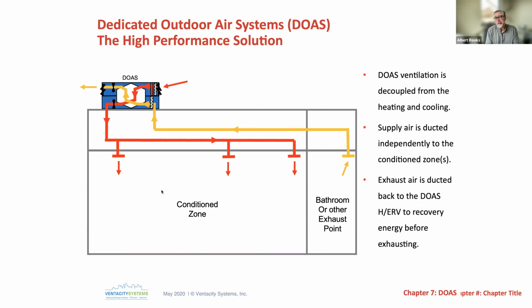Their typical equipment is in that 90% recovery range. And so when you're in that 90% recovery range, a simple application on the commercial side, not quite so much multifamily, but like a strip mall or something like that, one of those low flat buildings that's just got a sea of RTUs on the top. Essentially one of the studies they've done is go to a building like that, remove the RTU and replace it with one of these big blue HRVs or ERVs. And so now heating is gone, but ventilation is there, and it's ventilation with 90% heat recovery. They don't even change the building envelope. The building envelope is the same building envelope that it had before.